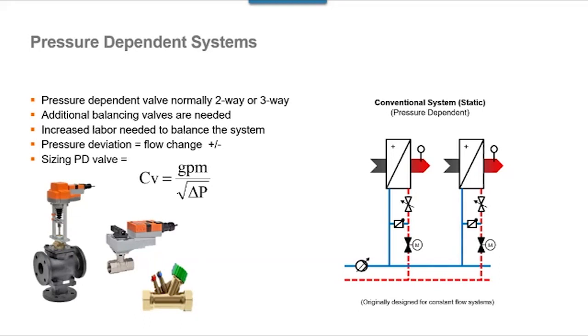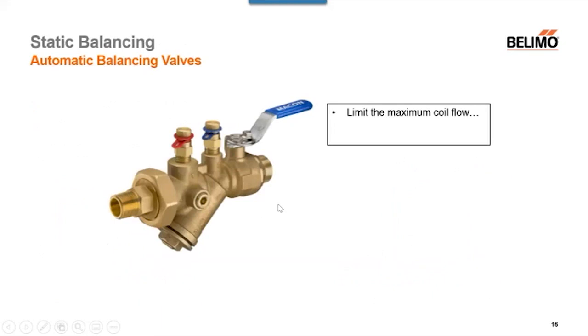Now, one of the things that helped along the way was the introduction of automatic balance valves. And I would imagine everybody on this call would agree with this statement. This was certainly a step up from the manual balance valve. But it's not entirely the overall solution, I guess I should say, because what an automatic balance valve is doing, it's limiting the flow. It's a flow limiter. So as the slide says, it limits the maximum coil flow. The big question, what happens when I'm below maximum flow?